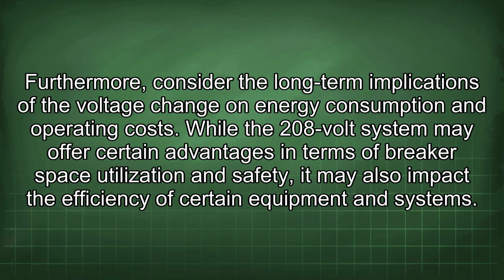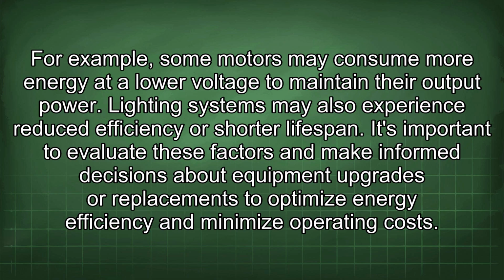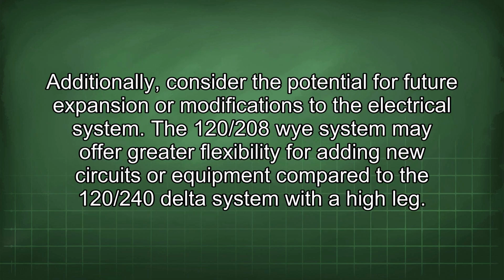Furthermore, consider the long-term implications of the voltage change on energy consumption and operating costs. While the 208 volt system may offer certain advantages in terms of breaker space utilization and safety, it may also impact the efficiency of certain equipment and systems. For example, some motors may consume more energy at a lower voltage to maintain their output power. Lighting systems may also experience reduced efficiency or shorter lifespan. It's important to evaluate these factors and make informed decisions about equipment upgrades or replacements to optimize energy efficiency and minimize operating costs.